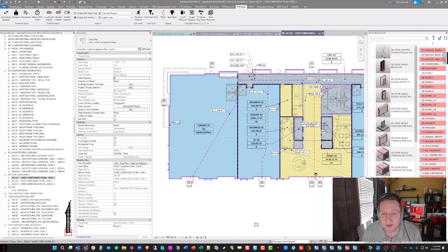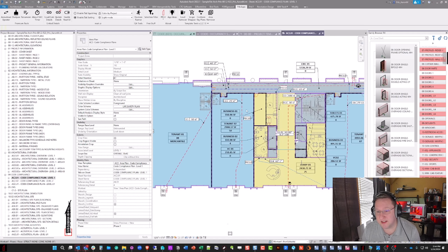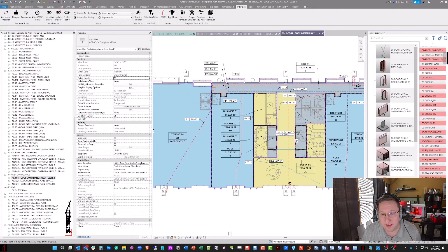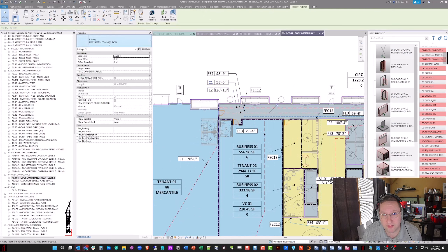If you want to, you can show things other than the name — such as occupancy type, occupants, and the name. It's not a requirement to show occupants in the tag because they are listed in the schedule at the top, but some AHJs have asked for it to be inside the tags, so we've built a way to do that. In addition, things like fire extinguishers and other relevant equipment just get a standard tag in the plan using an item type tag.